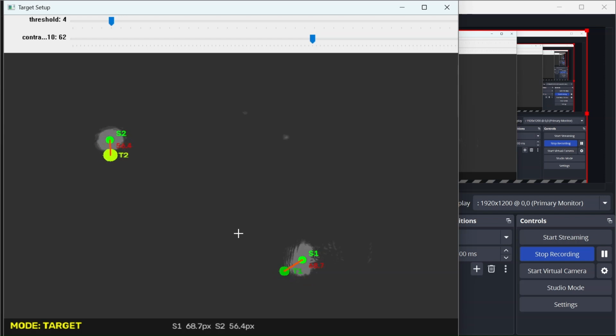Why is this information useful? Well, it's because knowing the distance and the error between the 2 spots gives us an indication of how much the beam stabilization software needs to correct. And there's also an option to jog the motors as well.